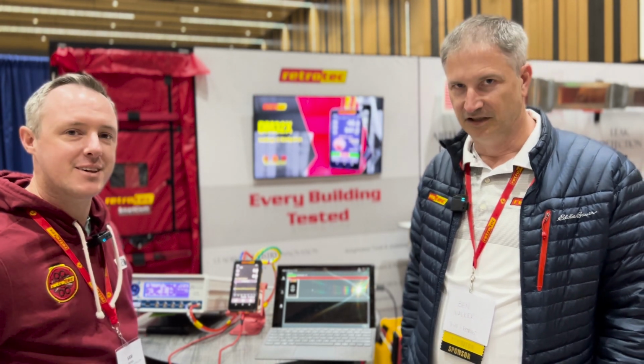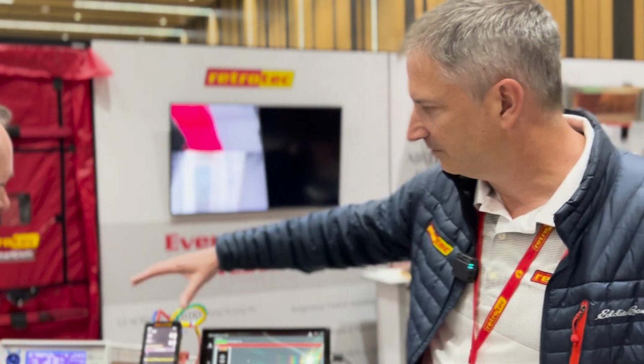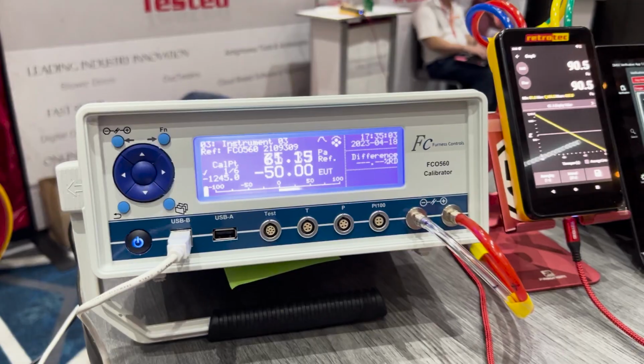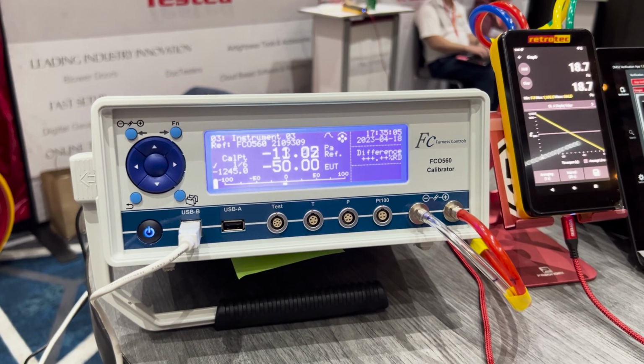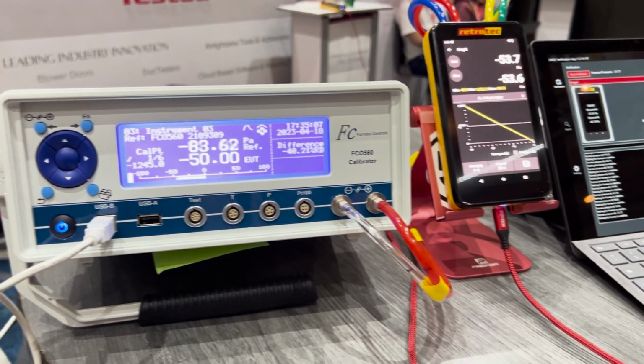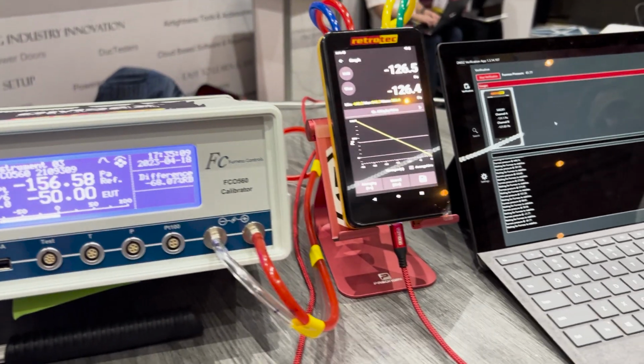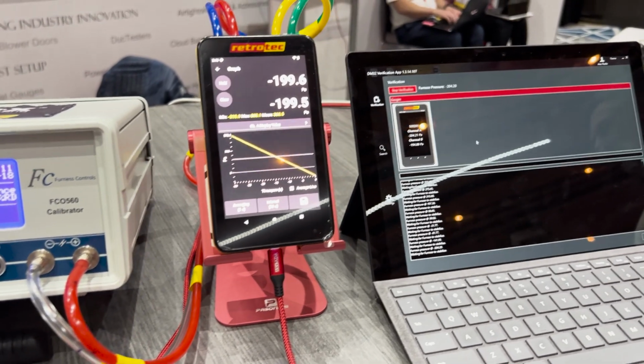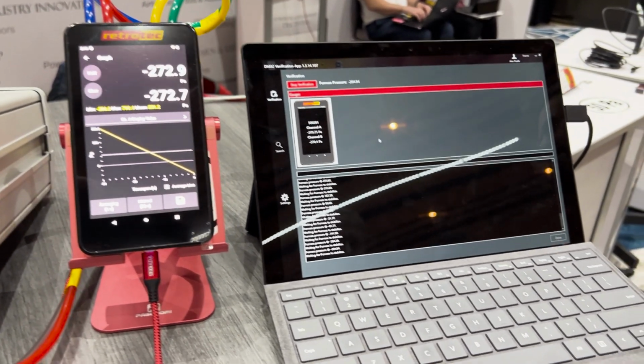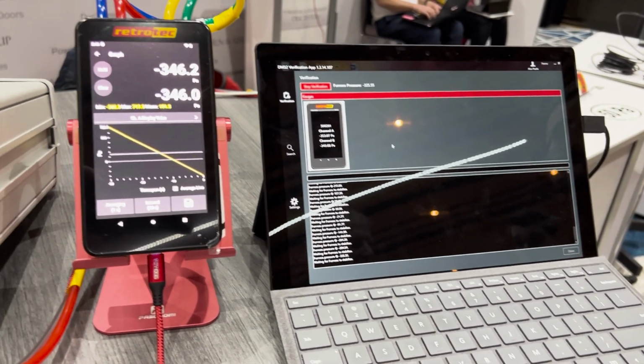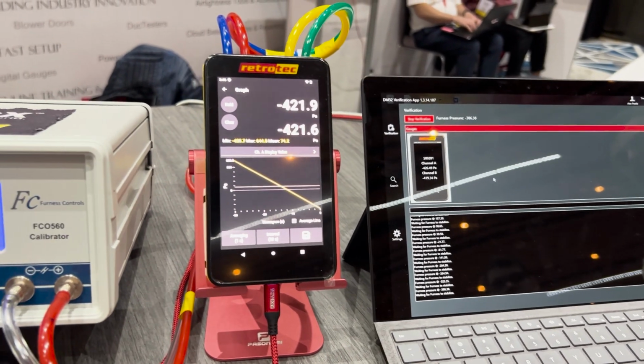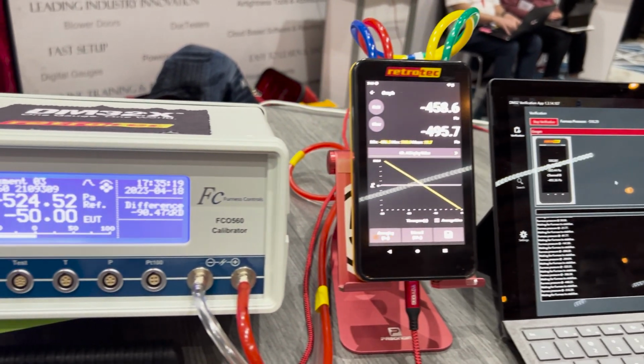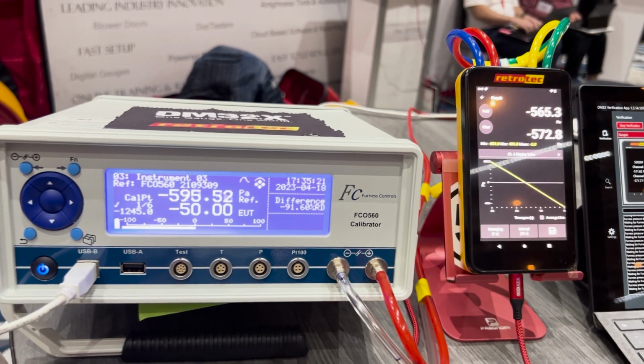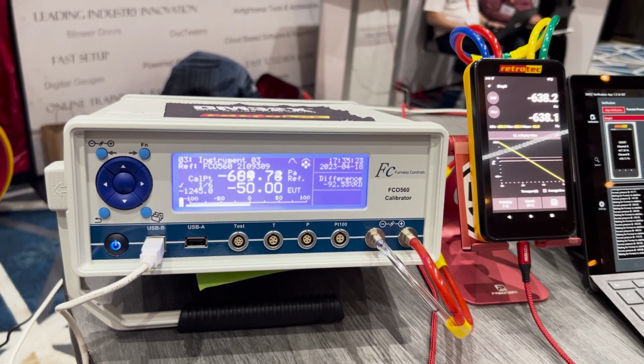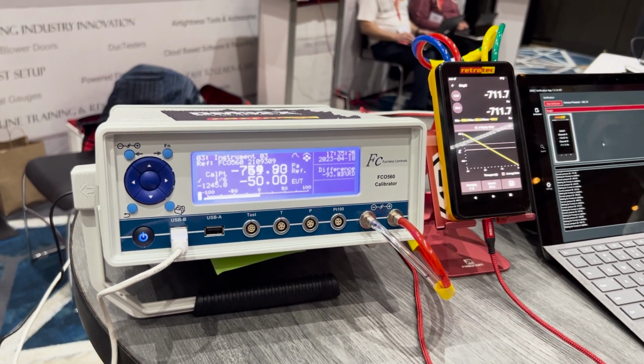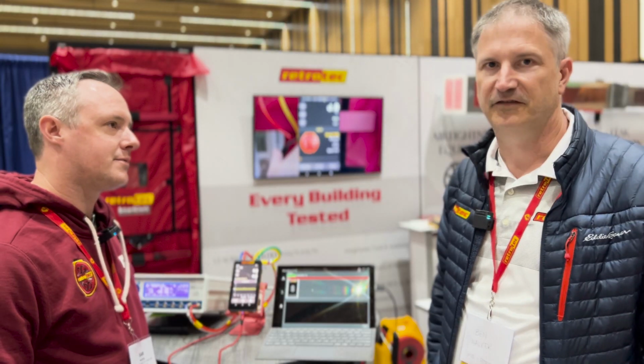Yeah, definitely. And the nice thing is that we have our Furness Controls, our master reference device here that we use. That's connected to the gauge, and that does a pressure comparison between the two devices, and then everything's computerized, so it goes through all the calibration points necessary to fully calibrate a DM32X or a DM32 or your DM2, and capture the calibration points by serial number, and then now you can go afterwards onto the website and get your updated calibration certificate to show in the field and everything.